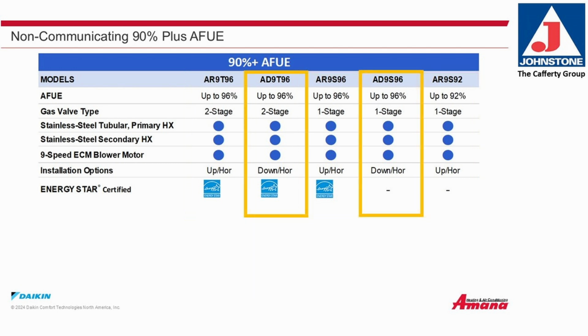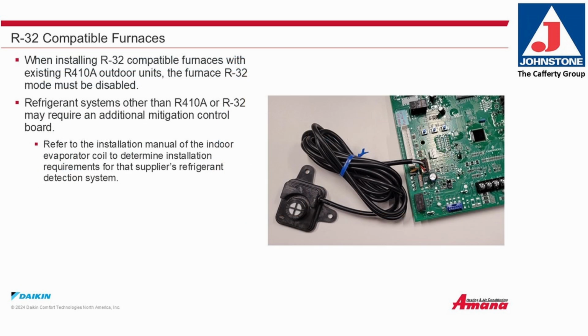The AD9T96, 96% 2-stage downflow horizontal furnace, and the AD9S96, 96% single-stage downflow horizontal furnace. R32 compatible furnaces. This furnace may be paired with a cooling unit that uses R32 refrigerant. If the cooling unit paired with this furnace does not use R32, the R32 function in the furnace control board needs to be turned off. Refrigerant systems other than R410A or R32 may require an additional mitigation control board. Refer to the installation manual of the indoor evaporator coil to determine the installation requirements for that supplier's refrigerant detection system.